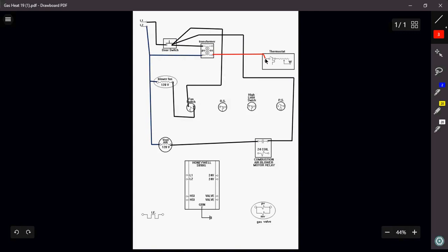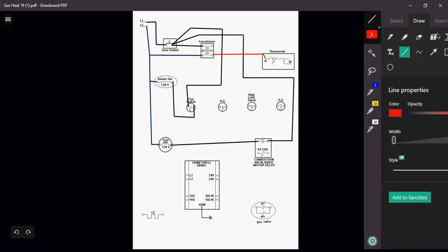So I'm going to come in and power up my transformer. Okay, so now what I need to know and what I need to understand is that my thermostat is my temperature sensing device that is in the space. It's what's going to close and tell my furnace that, hey, I need heat. But I need to make sure that my safeties are wired correctly so that I can have a safe working unit. So I have to do and understand my sequence of operation with my furnace. I got to understand how things are working.